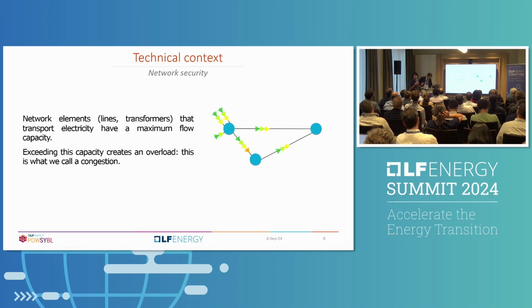Basically, if you have too much flow on the line, the line is going to heat up because of Ohm's law. As the line heats up, it expands, since it's basically a big cable of metal. As it expands, it gets closer to the ground, and at some point it becomes too dangerous. That's why we have a limit on every line of the network.